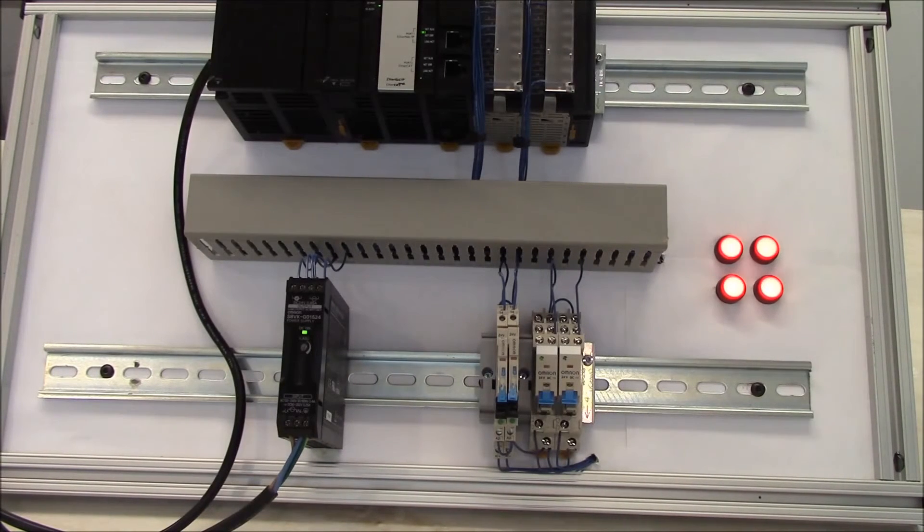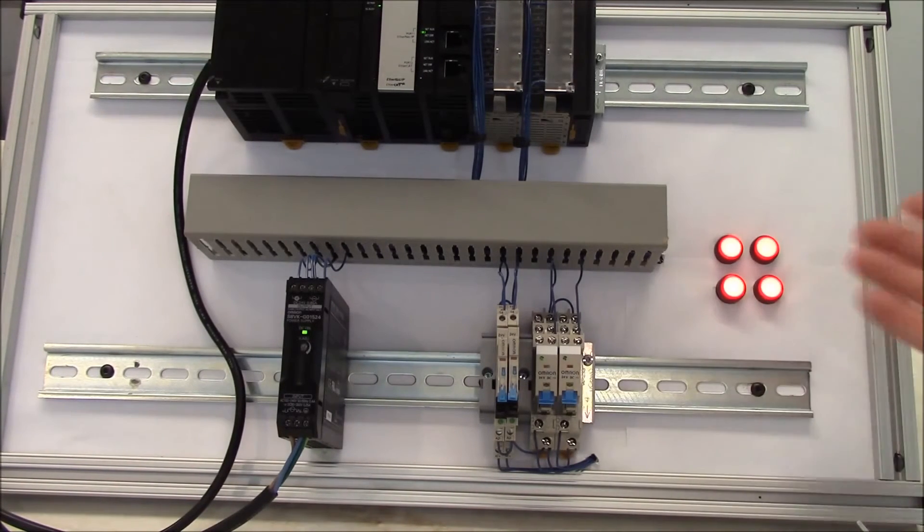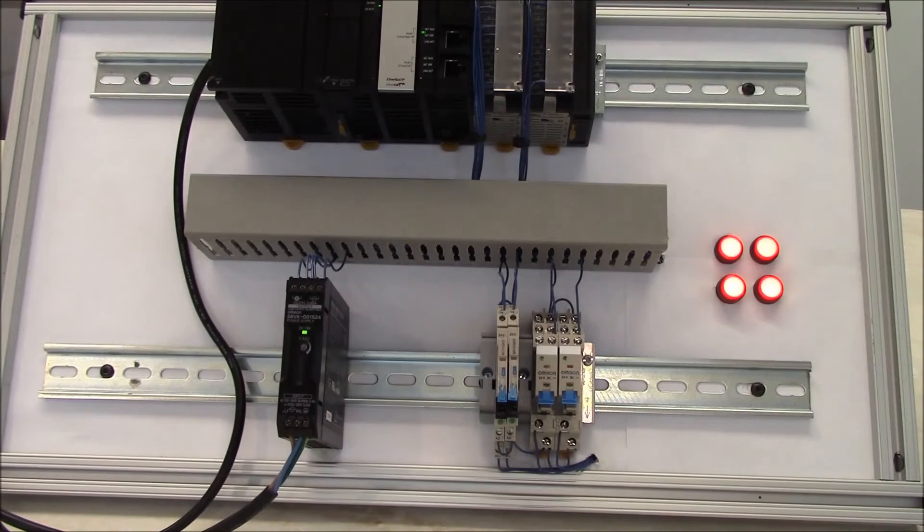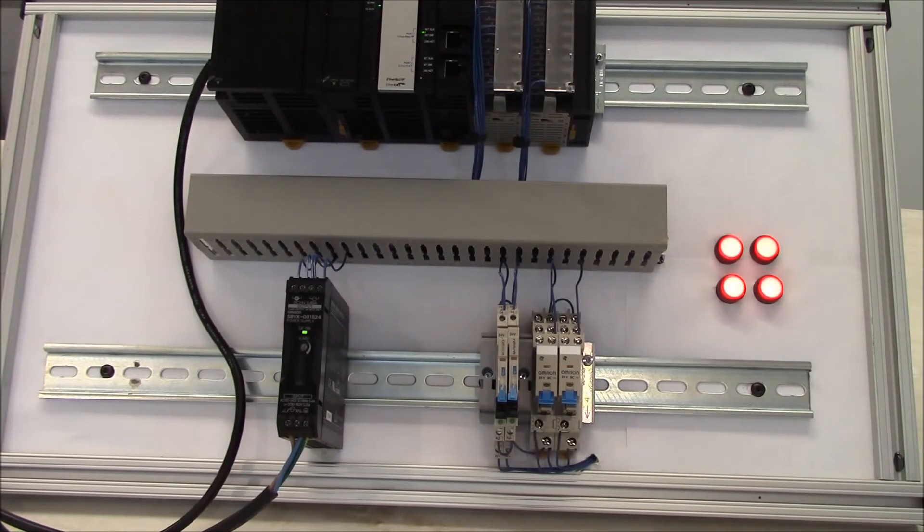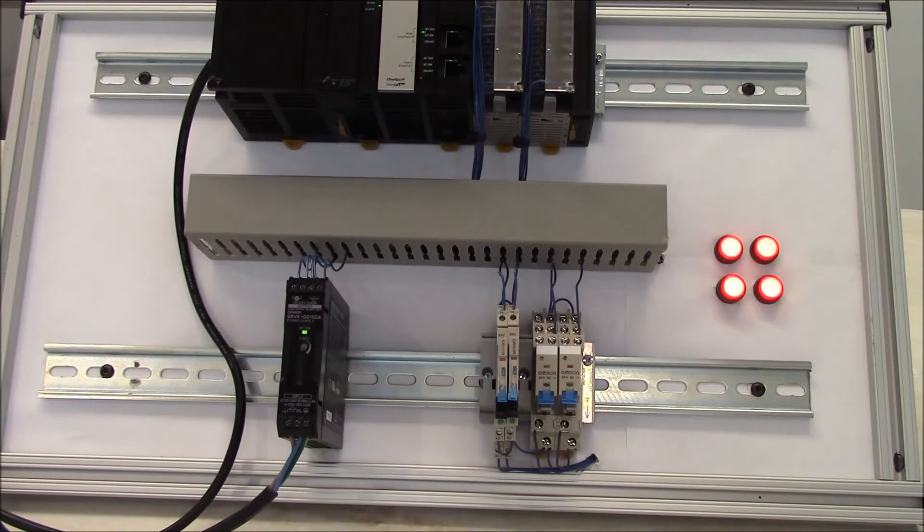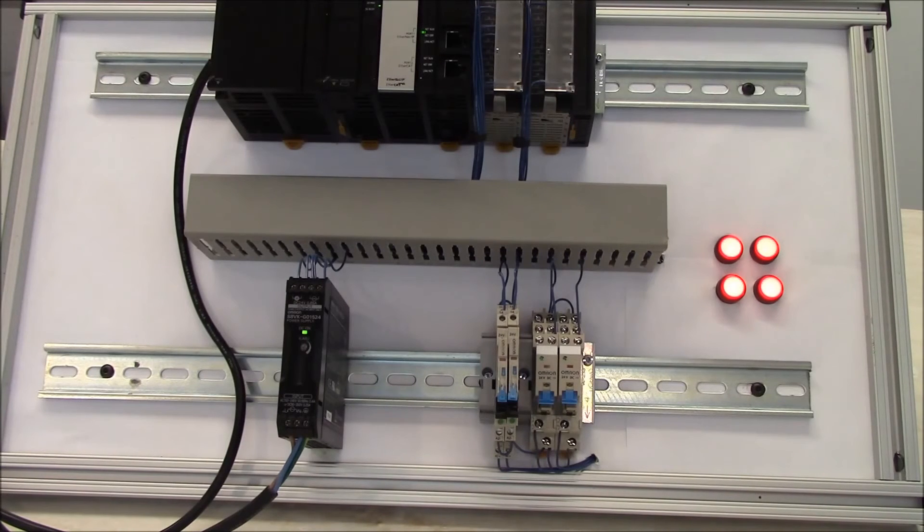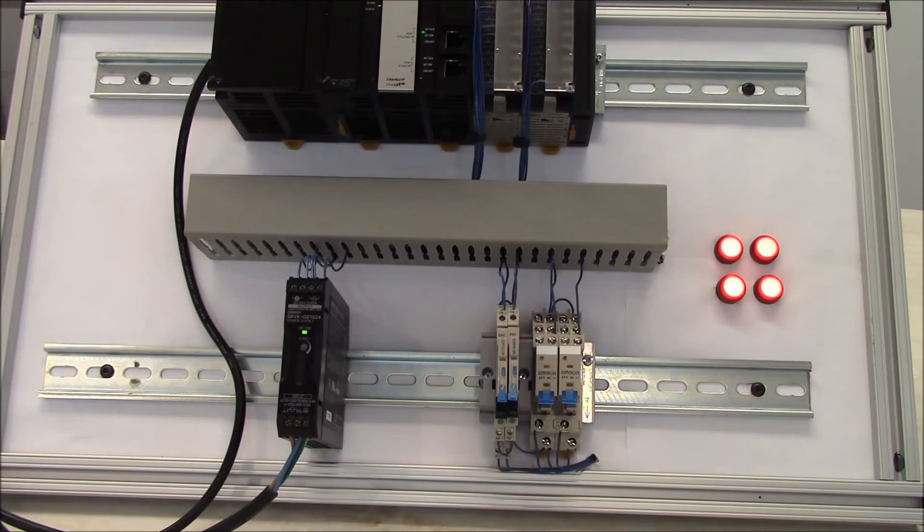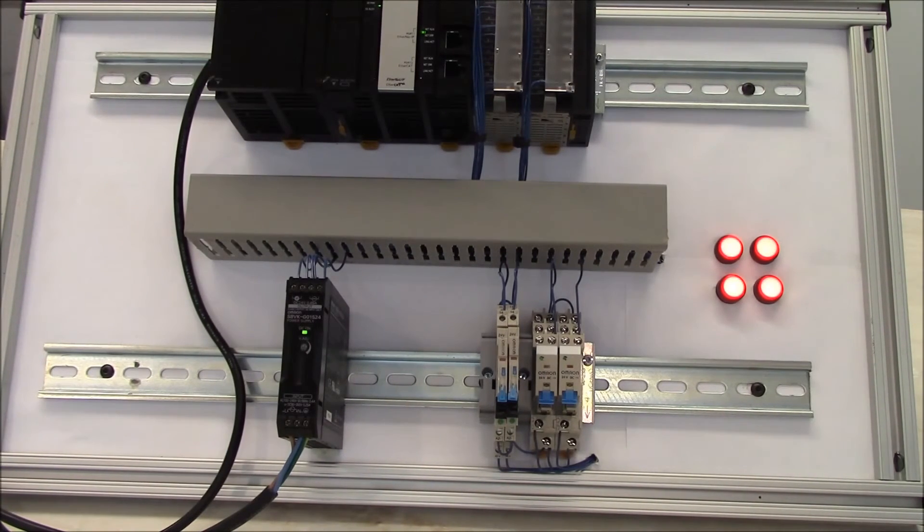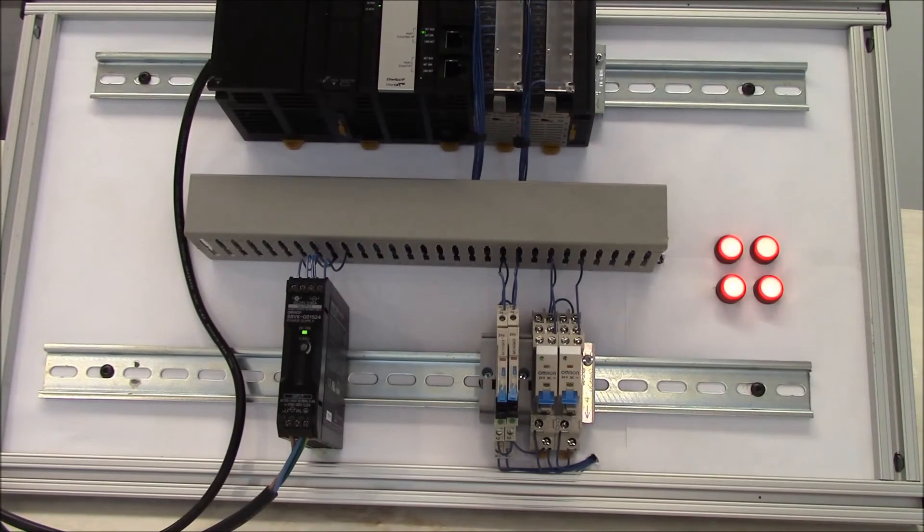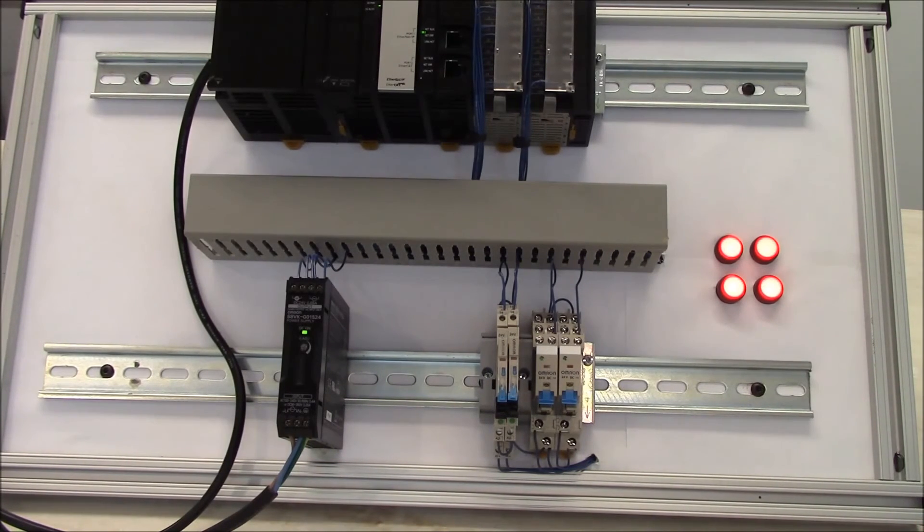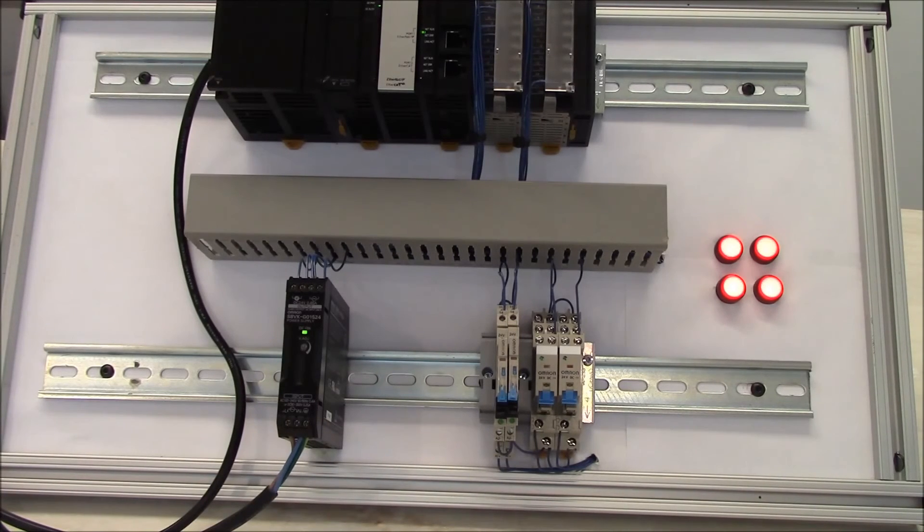I can test to make sure that my wiring from the relay output to the devices are set correctly. Let's say for example, if I have the outputs wired to a pneumatic cylinder, I can sit there and I can actuate the cylinder, make sure my air flow valves are set proper before the programmer even gets down. Or if it's on a pneumatic or hydraulic application, I can make sure the pressures are all set right.